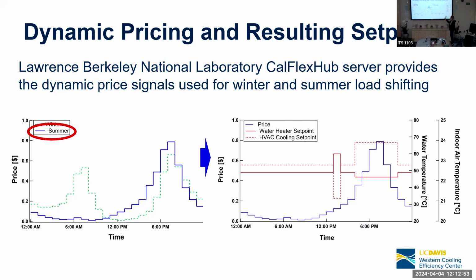And another alteration we made within our algorithm prior to this, all of this time would have been either an elevated water heater or reduced HVAC cooling set point, which is unnecessarily energy intensive. And also, sometimes you get a situation where you're not pre-cooled or preheated in the case of the water heater immediately going into the load shift period. So we delay that to the final hour before the set points start to reduce. There's also a small change which encourages simultaneous AC and water heating: if we ever have a call for water heating, this HVAC cooling set point will decrease by 2 degrees to force the system into the dual HVAC and water heating mode to take advantage of that energy efficiency increase.